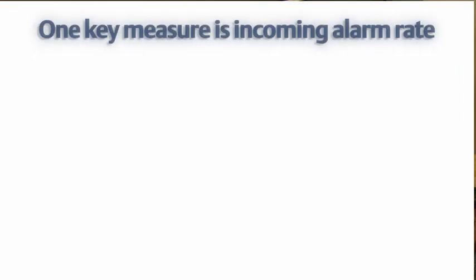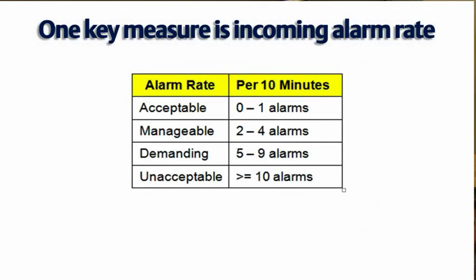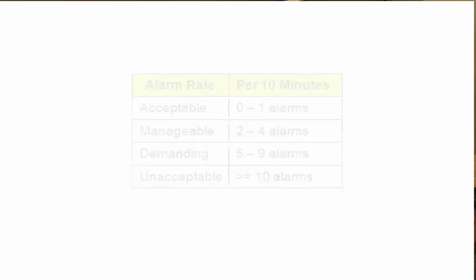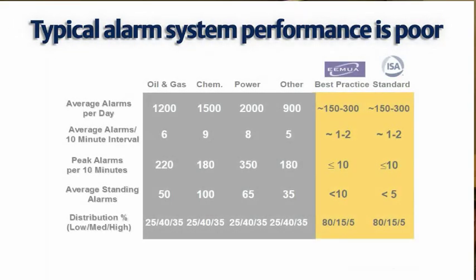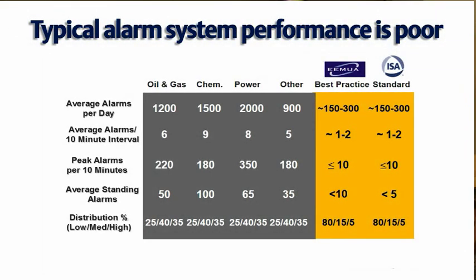This standard contains normative clauses for what constitutes good alarm practices and so these are auditable measures of managing alarms. The key measure for alarm management is the incoming alarm rate and these are the benchmark defaults. The typical performance in the industry is far short of these benchmarks. Typically you can see as many as a 10x incoming alarm rate to what is an actual optimum or acceptable alarm rate.